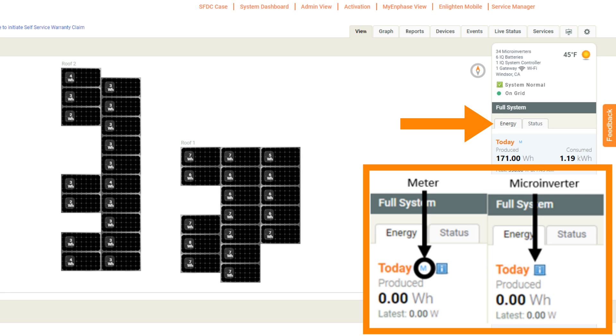Also, in the View tab section of the installer portal, look for Energy in the right-hand column. If an M is displayed next to today, you are viewing the meter production measurements. If the M is missing, you will be viewing the microinverter production measurements.